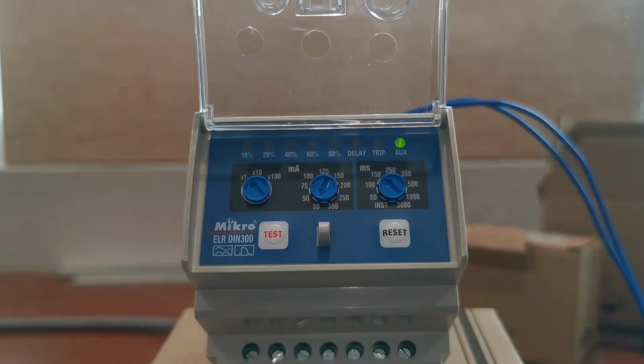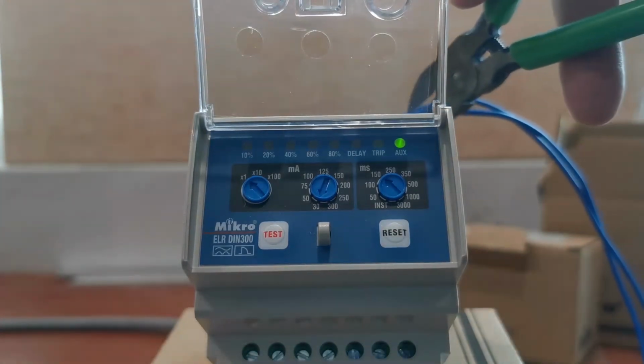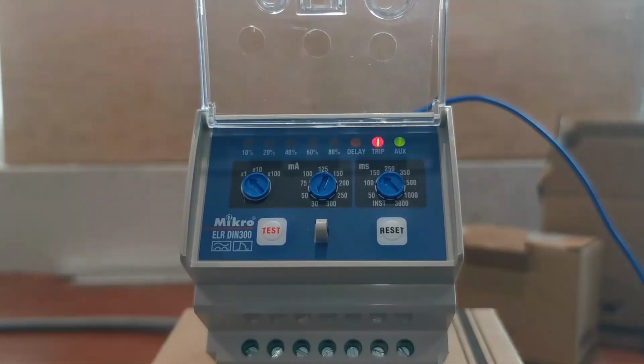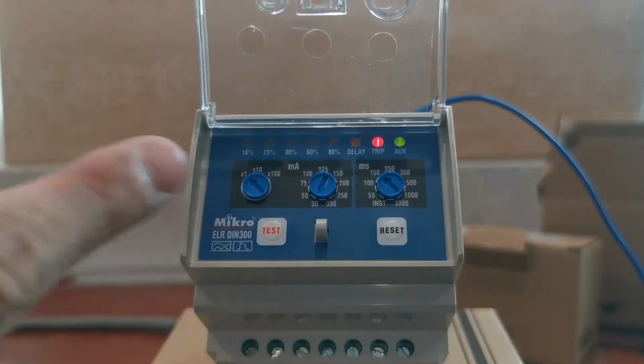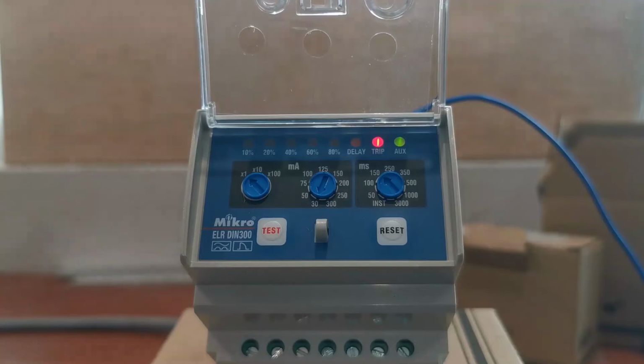This earth leakage relay will also have an alarm when the connection from the earth leakage relay to the zero sequence current transformer, ZCT, is broken. So I will demonstrate this. As you can see, the relay trips when it detects that the ZCT is disconnected and the display will start to blink.